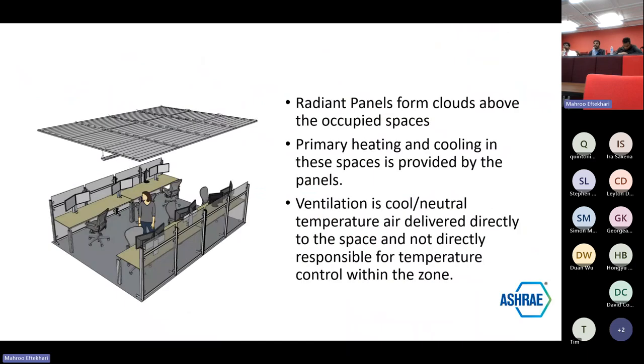We had these radiant panel clouds above the occupant space. They were actually around the perimeter and could do heating or cooling there. In the interior zone, it was cooling only, in a cloud-like arrangement. The ventilation was kept cool-neutral from the DOAS unit, on the cool side of neutral, so it could be varied slightly, but we didn't want to rely on it for cooling.